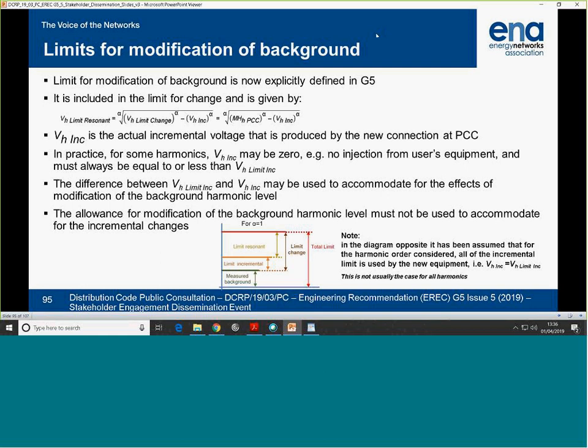The feature of this, which was missing in G5/4, is the amplification effect. It's been found that at most of the HVDC transmission level, and I'm sure at 33 kV level, there is always a piece of cable involved, so it modifies the harmonic profile at the point of connection. G5/4 didn't have anything explicit on that. There are some references in ETR 122, but G5/5 brought that into the main body of the document. So the total effect of the connection includes amplification of the background, and part of the limit.